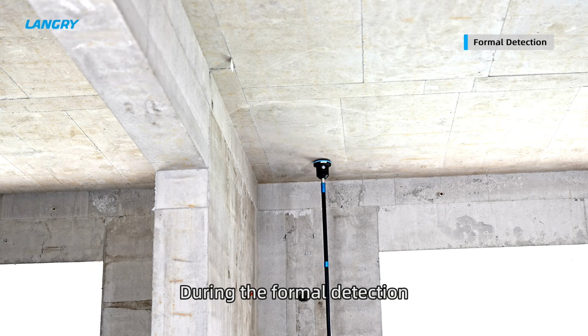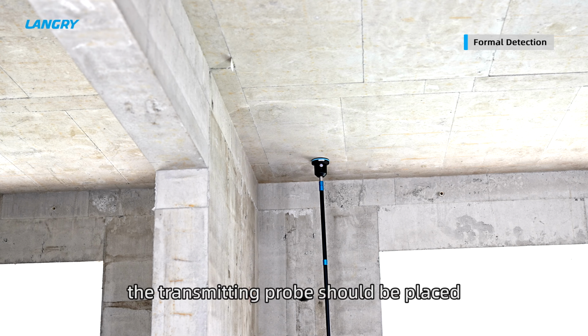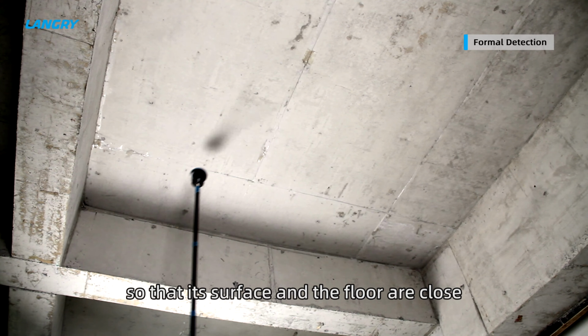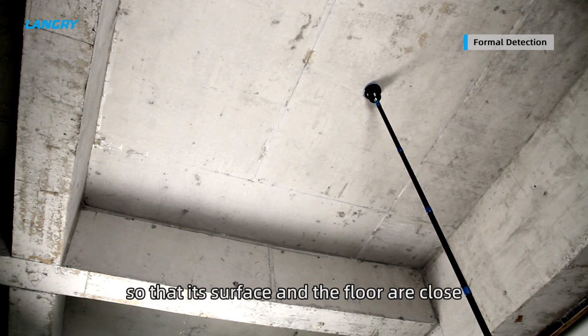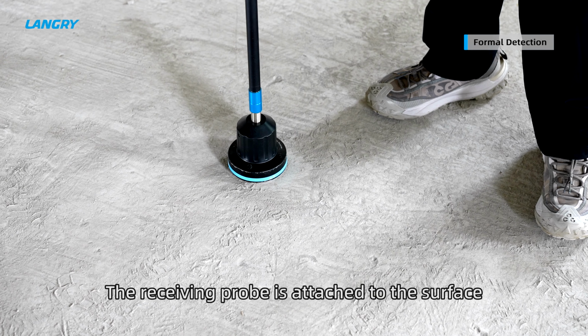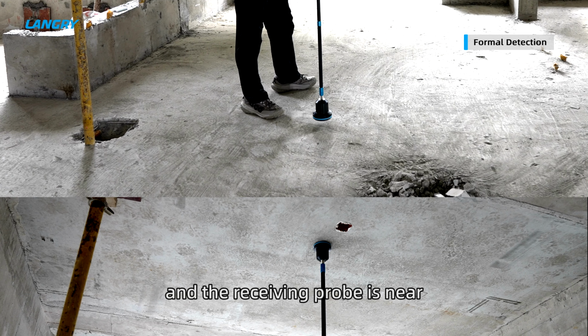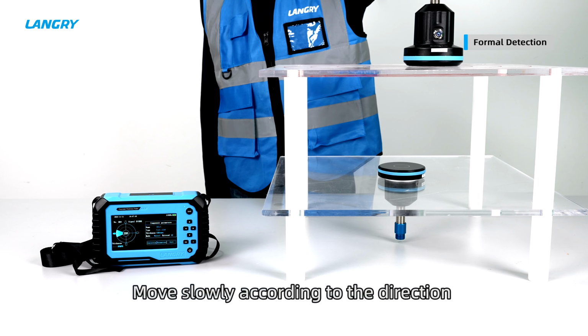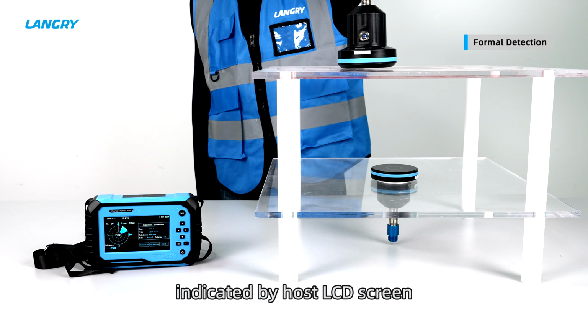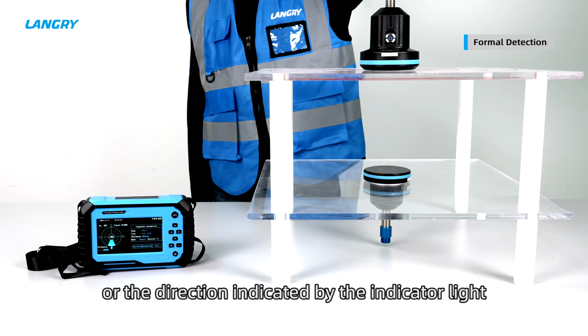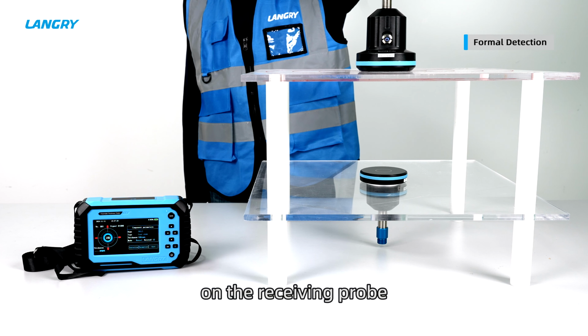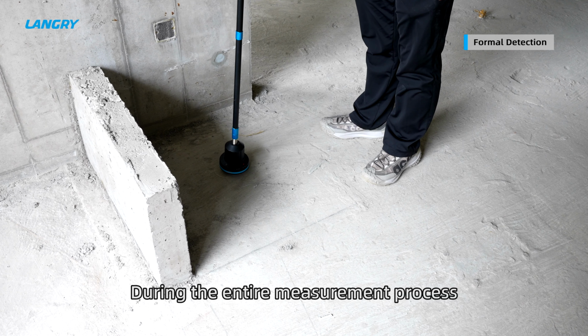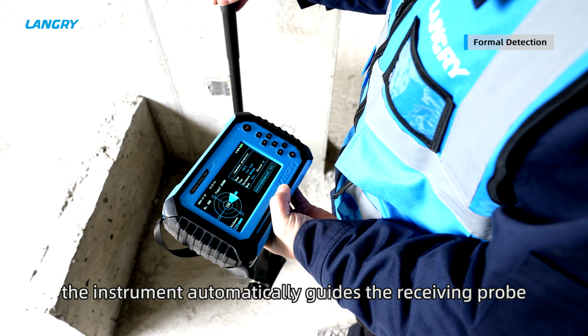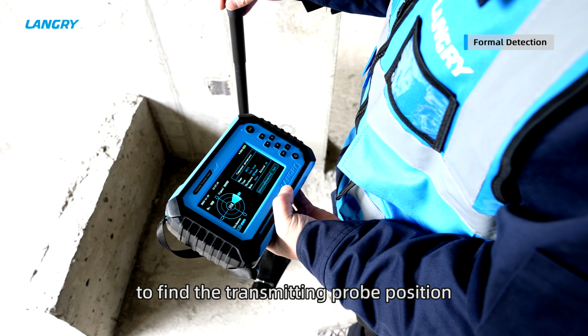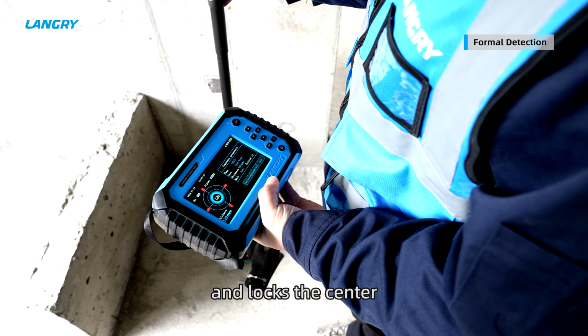During the formal detection, the transmitting probe should be placed on the bottom of the floor to be measured, so that its surface and the floor are close. The receiving probe is attached to the surface of the floor under test, and the receiving probe is near the top of the transmitting probe. Move slowly according to the direction indicated by the host LCD screen, or the direction indicated by the indicator light on the receiving probe. During the entire measurement process, the instrument automatically guides the receiving probe to find the transmitting probe position, and locks the center.